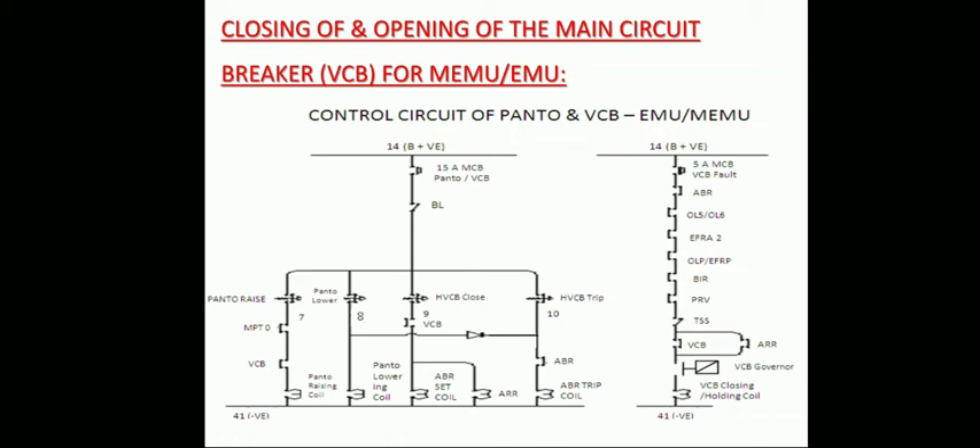The path to the VCB closing coil is now maintained through the 5-amp MCB for VCB fault, ABR which is latched, OL5 and OL6 closed interlocks, EFRA 2 closed interlock, OLP and EFRF closed interlock, BIR closed interlock, PRV closed interlock, TSS closed on run, VCB interlock, and VCB governor.